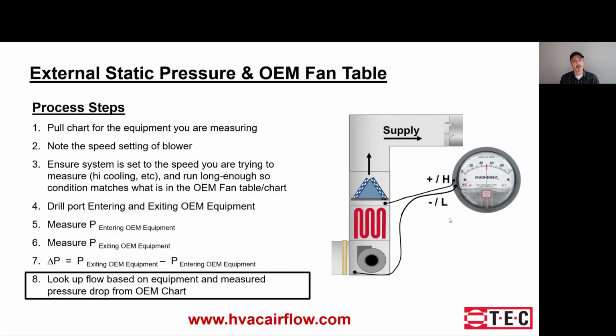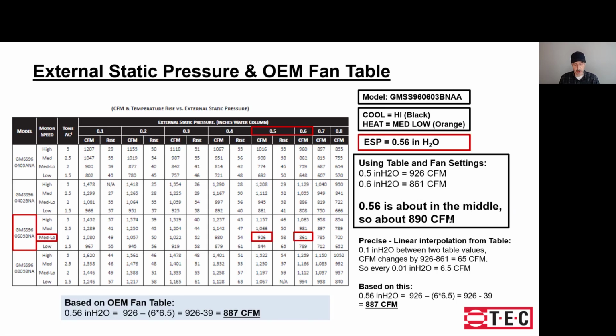So now we're ready to go back to the table we pulled for the Goodman furnace that we have, and we'll convert it. So remember earlier we had the model number and the speed setting defined. It was medium low, and we just said that we had a measurement of 0.56 inches of water column, or inches H2O. So in the table there's both a 0.5 column and a 0.6. So making a note, at 0.5 it would be 926, and at 0.6 it's 861.